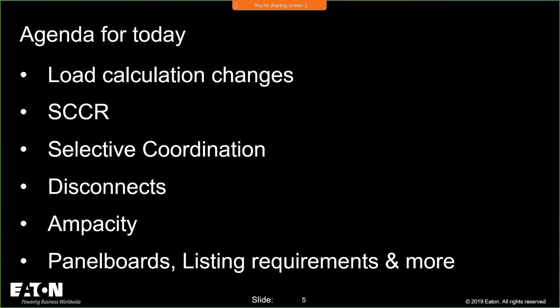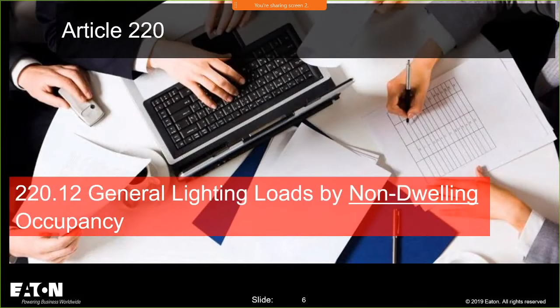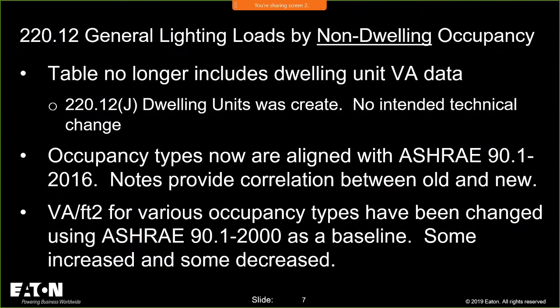Let's move on into the program. The first section we're going to cover is 220.12. There were some big changes in 220.12. There was a task group associated with this. And if you look at 220.12, I'm just opening my code book, as I know everybody out there is opening their code book to 220.12. If you look, we changed the title from the 17 cycle to the 20 cycle, and we removed the dwelling unit.